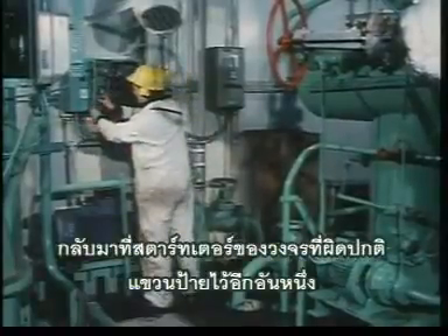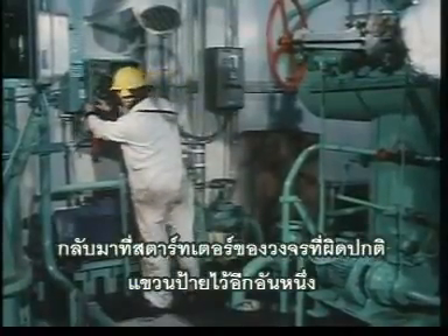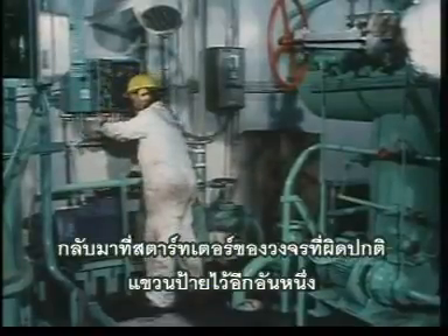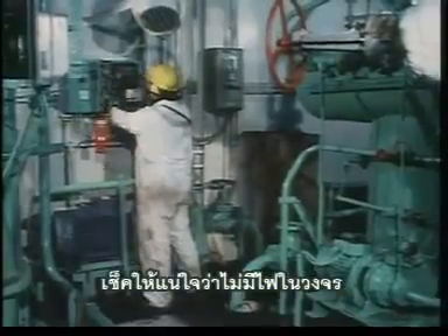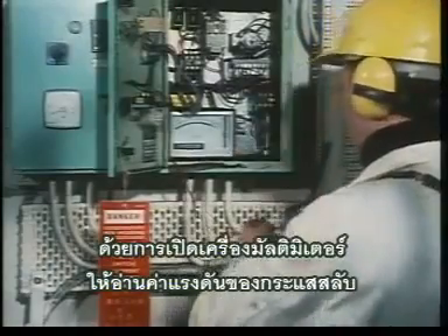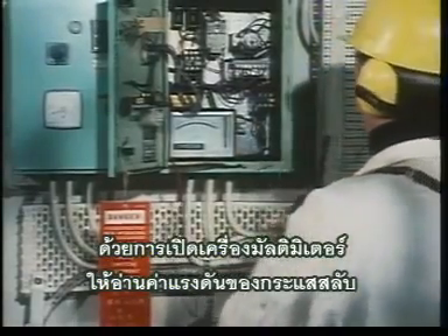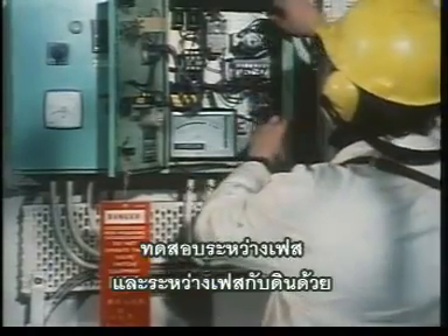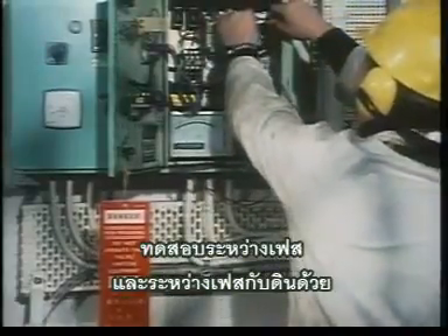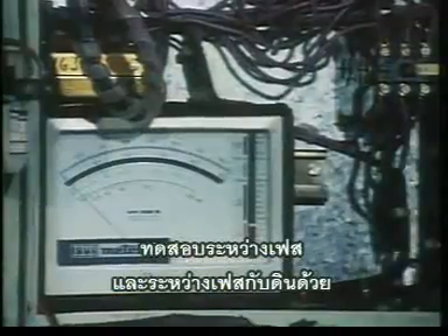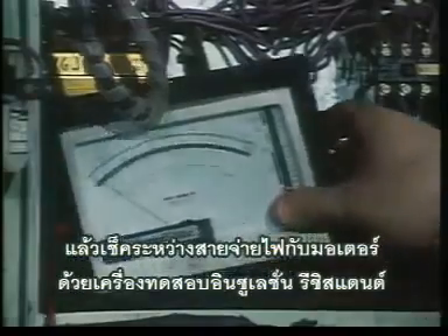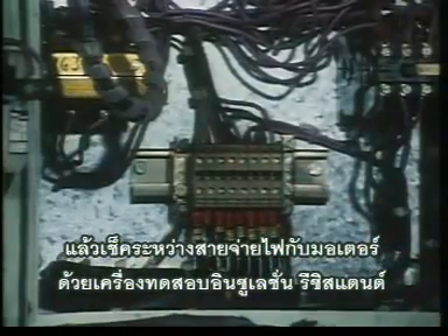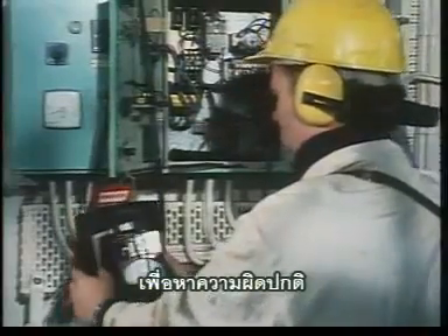Back at the starter of the faulty circuit, another notice is posted. And the circuit is checked for being dead by a multimeter set to read AC volts. The test is between phases as well as between phases and earth. Then the feeder cables to the motor are checked by an insulation resistance tester for the presence of the fault.